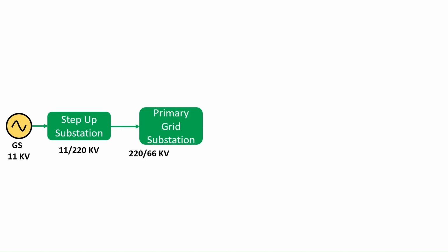From the step-up substation, electric power at 220 kV is transmitted by a three-phase three-wire overhead system to the outskirts of the city. Here, electric power is received by the primary grid substation, which reduces the voltage level to 66 kV for secondary transmission. The primary grid substation is generally of outdoor type.